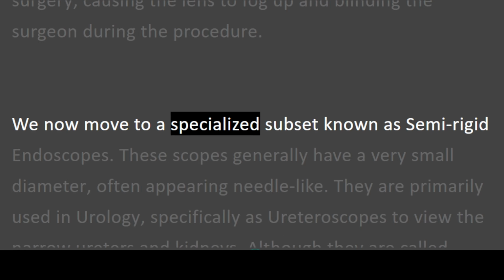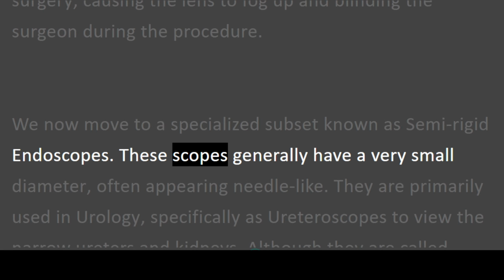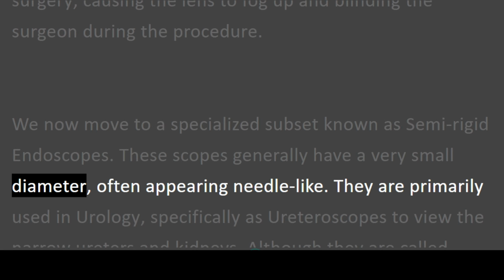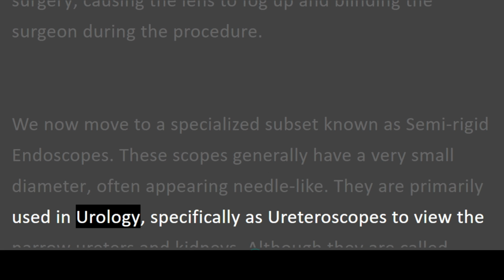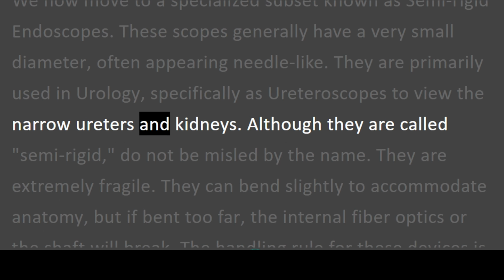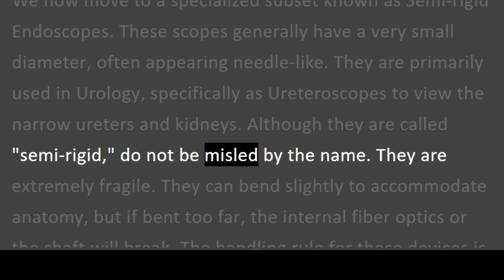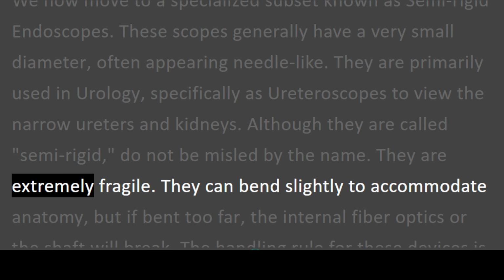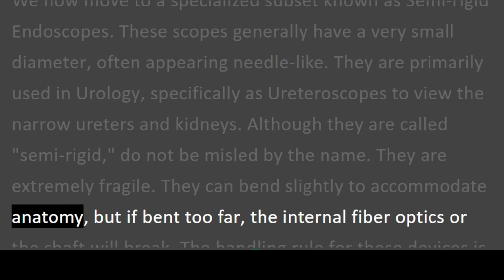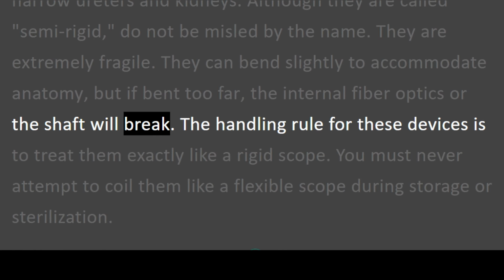We now move to a specialized subset known as semi-rigid endoscopes. These scopes generally have a very small diameter, often appearing needle-like. They are primarily used in urology, specifically as ureteroscopes to view the narrow ureters and kidneys. Although they are called semi-rigid, do not be misled by the name. They are extremely fragile. They can bend slightly to accommodate anatomy, but if bent too far, the internal fiber optics or the shaft will break.